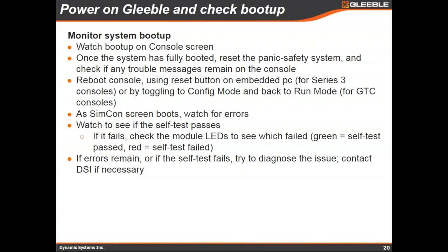As it's booting, watch the console screen for errors — it might say something like 'Module 12 error' or 'oil level high.' Also watch the self-test and see if it passes or fails, though it may move too quickly to catch everything. You can then check the LEDs on the front of the modules in the console slots — green means the self-test passed for that module, red means a component failed, either the zero test or upscale test. If there are errors or self-test failures, do your best to diagnose the issue and contact DSI as necessary.